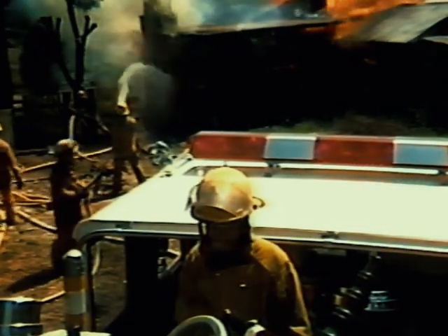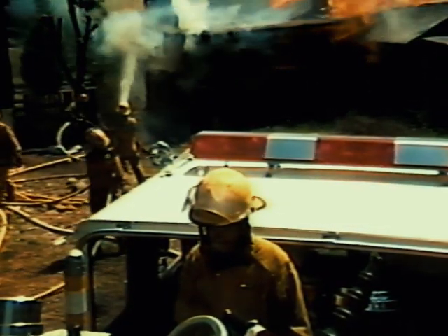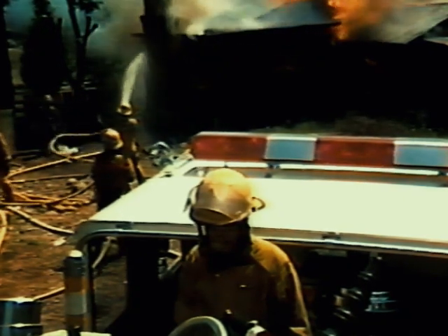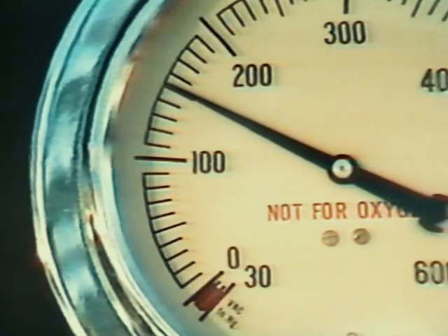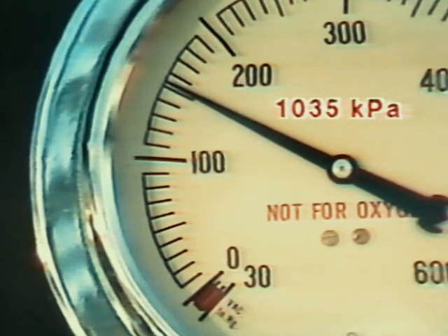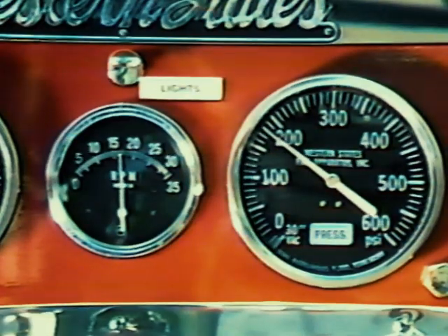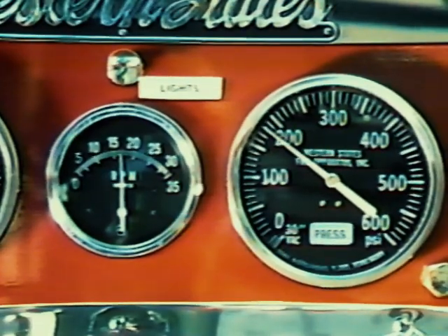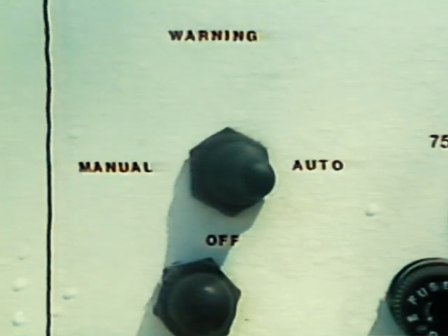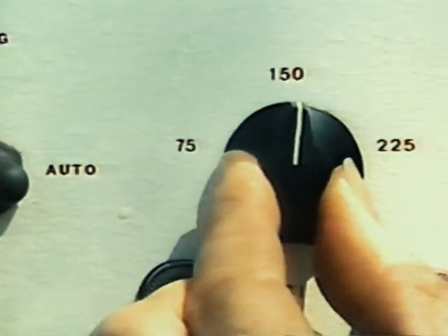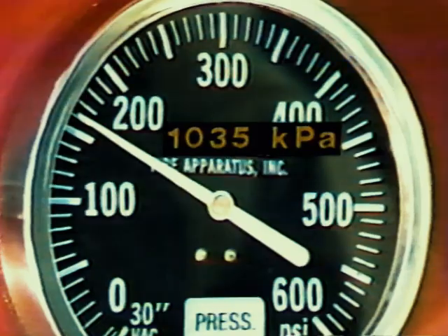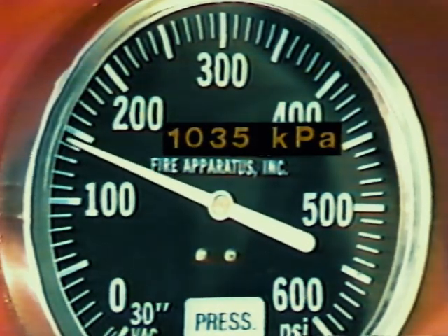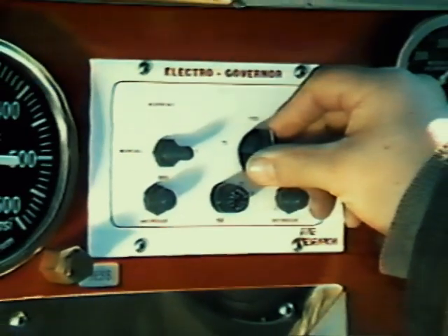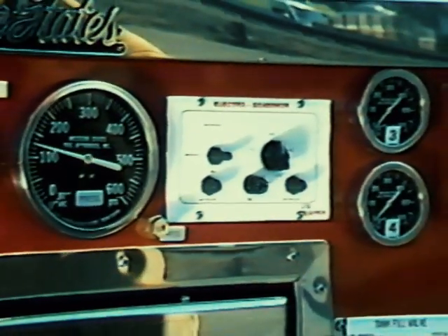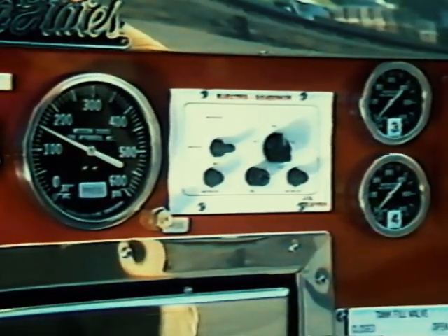To operate a pressure governor, the pump should be running and flowing at desired pressure and quantity, with the hose lines open. For example, if the desired pressure is 150 psi, turn the pressure control knob until the pump is pumping slightly above the desired operating pressure. Activate the governor by opening the governor valve or pressing the actuator. Turn the pressure control knob back and reduce discharge pressure to the original pressure of 150 psi. The governor is now set and will increase or decrease the speed of the engine to maintain the preset pressure.